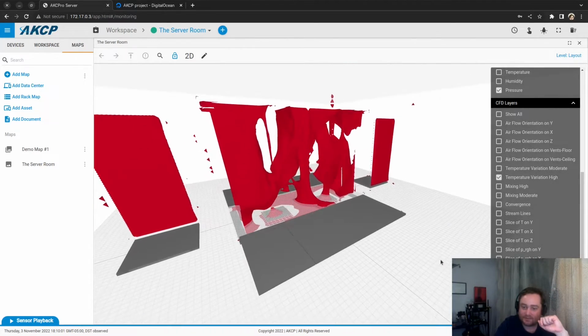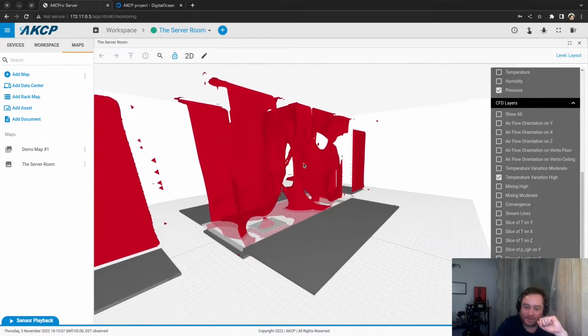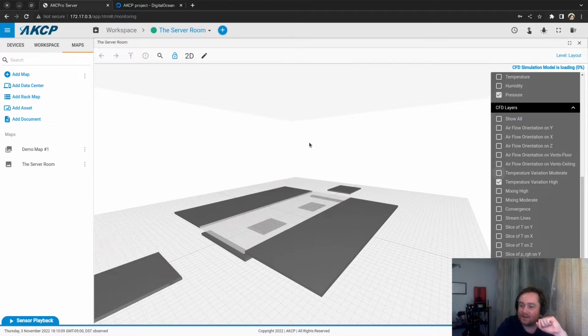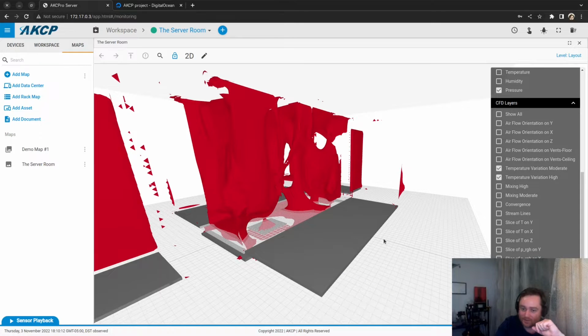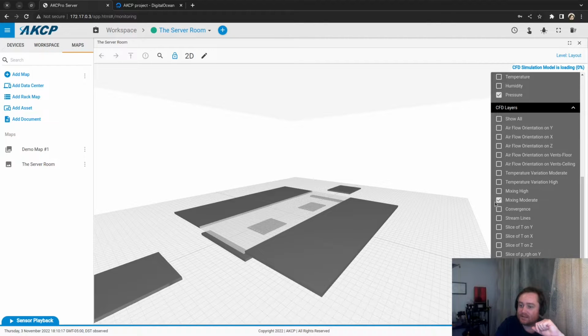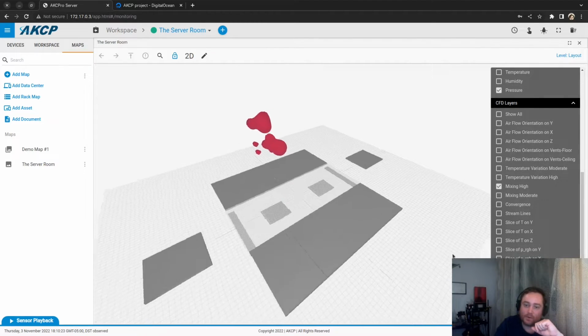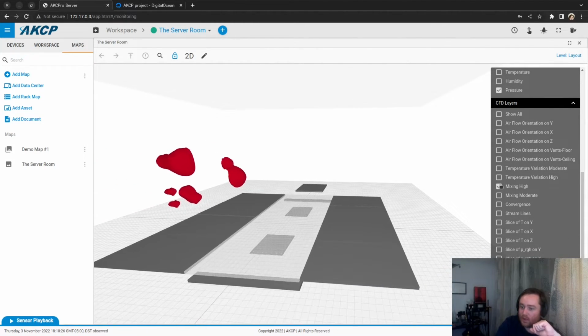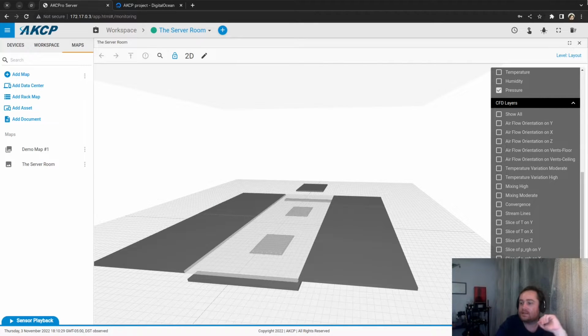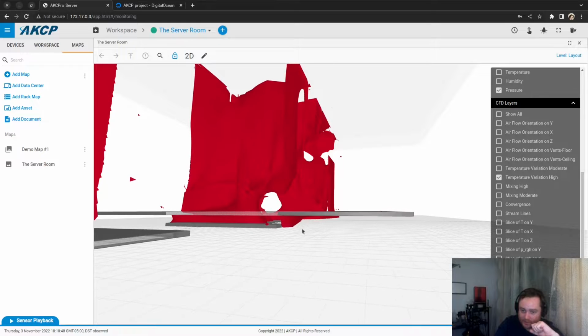So when you see a lot of red like that, something is wrong with the containment. The red represents a great difference of temperature. So we know that the air enters under and mixes there. Those are not exactly mixing in temperature. It's turbulence, a lot of turbulence in the air. So yeah, it's not the same tool. That one is really the one you want to use to see if there is mixing of cold and hot air. So we have our air that enters there and mixes.